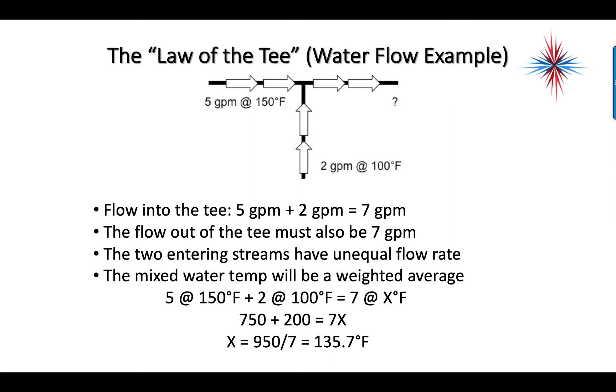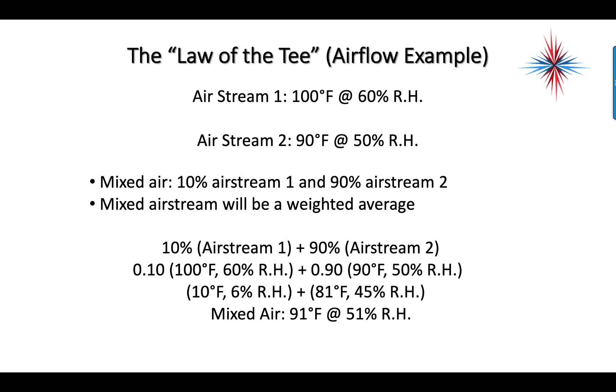Now let's look at airflow, because that's really what we're talking about with psychrometrics. We have airstream one, which is 100 degrees Fahrenheit at 60% relative humidity, and airstream two, 90 degrees Fahrenheit at 50% relative humidity. Our mixed stream is 10% airstream one and 90% airstream two. The mixed airstream has to be a weighted average, just like what we did. So we have to take 10% of our 100 degree, 60% relative humidity air and 90% of our 90 degree, 50% relative humidity air.